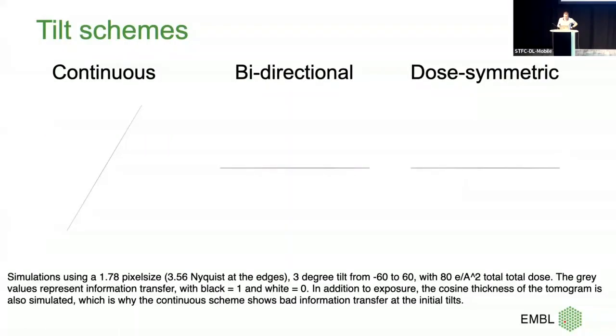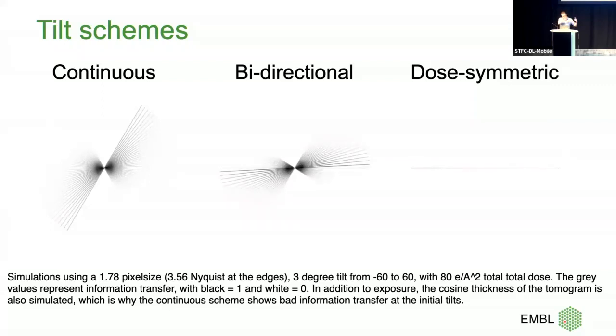That's where I started thinking about tilt schemes. The first historically was a continuous tilt scheme: start at high tilt and go to the other side. In cryo the problem is you first have to tilt up to that high tilt while tracking — tricky. Then people said: let's do bi-directional — start at zero, tilt one way, sweep back, do a realignment step, do the other side — which is where we saw the damage. So I asked: what if you use a dose-symmetric tilt scheme?